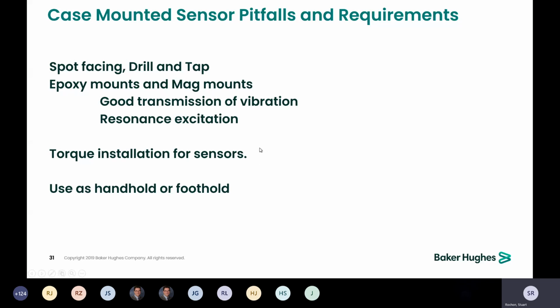Most of these sensors have a very small torque installation spec. It's generally in the inch-pounds of torque for installing these. Having somebody out there with a large wrench twisting these down, getting them really tight, tends to shatter the crystal inside. So whenever you're installing these, take a look at the data sheet, find out what the torque setting is, use a torque wrench, and install them properly, just to keep from damaging the sensors.